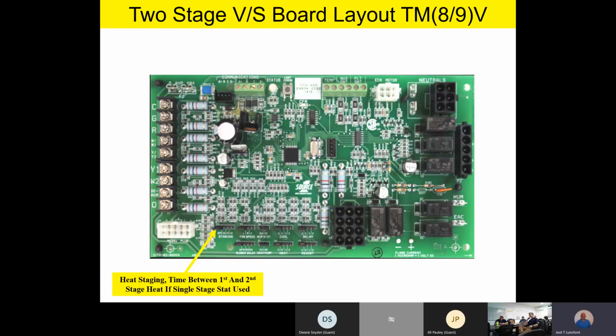Now this is really, really important. If you're stuck with a single stage thermostat, make sure it's on something other than off. Because if it's in the off position with a single stage thermostat, in other words, all you have hooked up is W1, W/W1 on the board. You're stuck with a single stage thermostat, you don't have enough wires, the homeowner doesn't want to change the thermostat for whatever reason. You're stuck with a single stage heating thermostat. If that's in the off position, you will never get out of first stage heat.